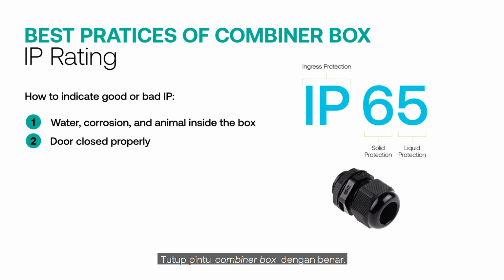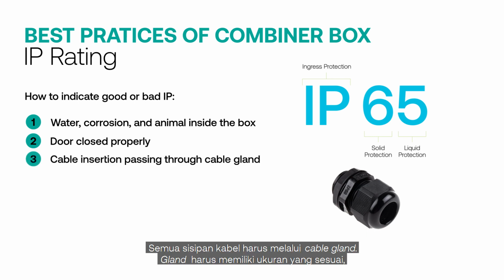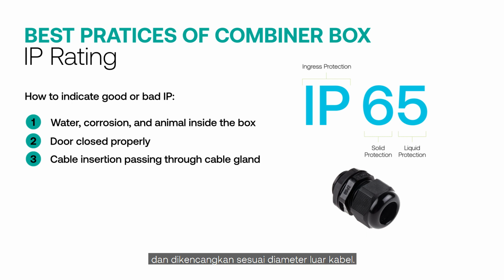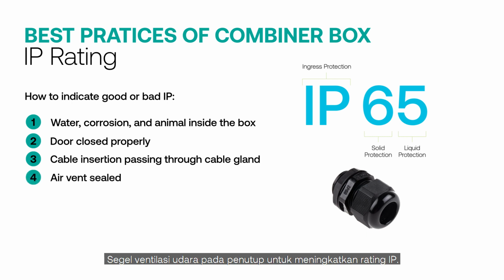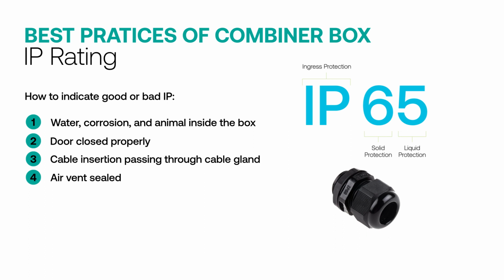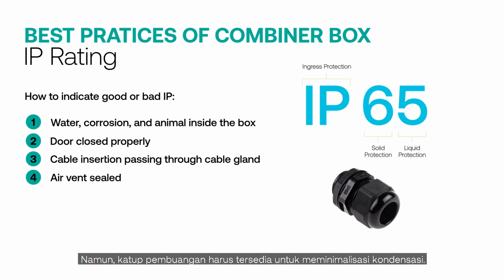Close the door of the combiner box properly. All cable insertions should pass through a cable gland. The gland must be correctly sized and tightened corresponding to the outer diameter of the cable. Do not put several cables through a single gland. Seal the air vent on the enclosure to increase the IP rating. However, a drain valve or breather should be provided to minimize condensation.